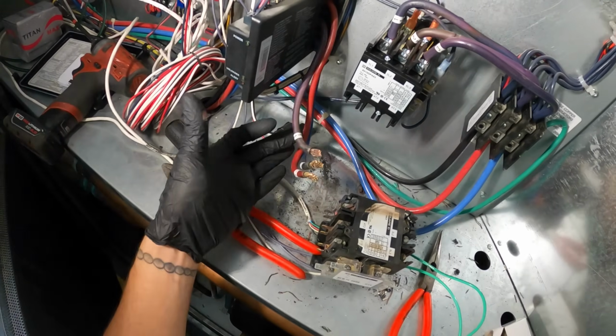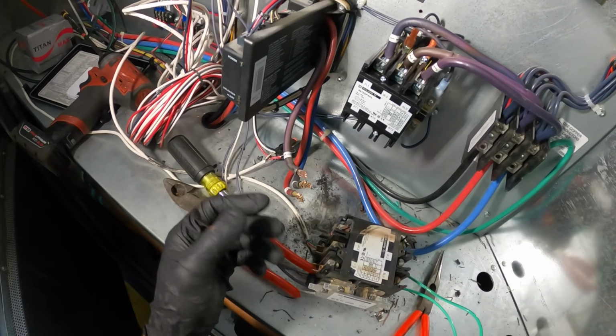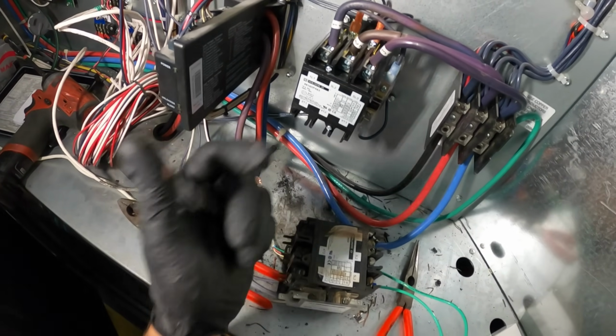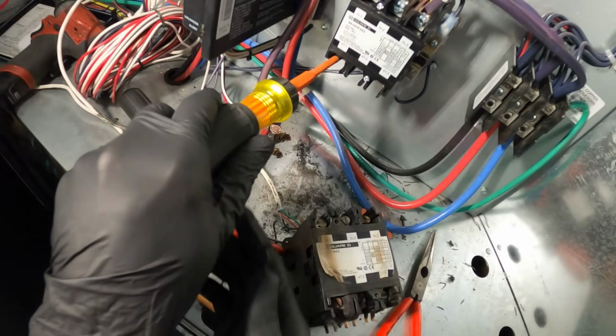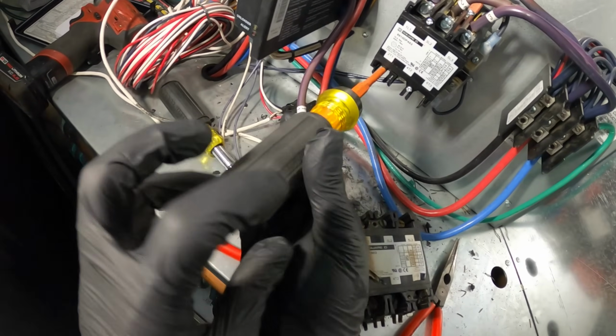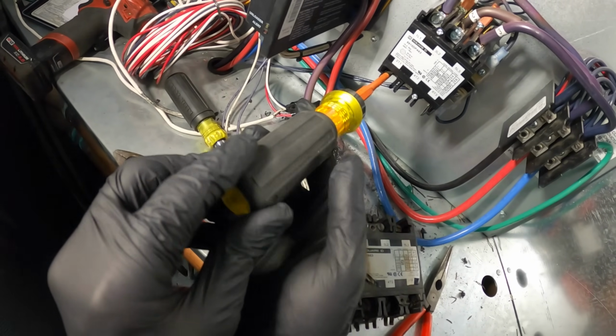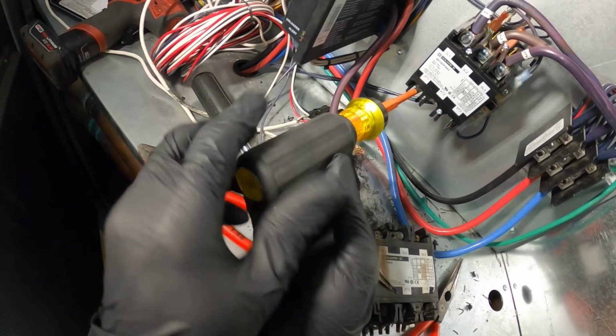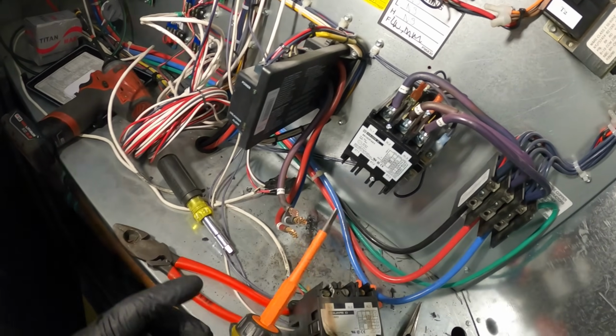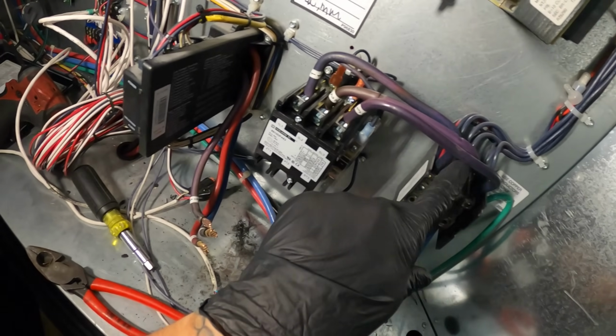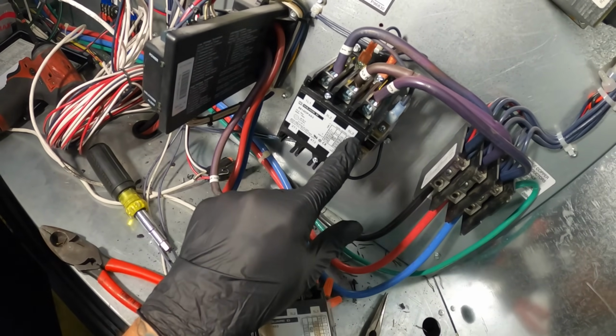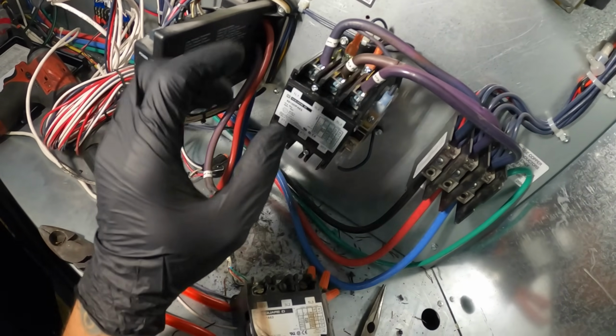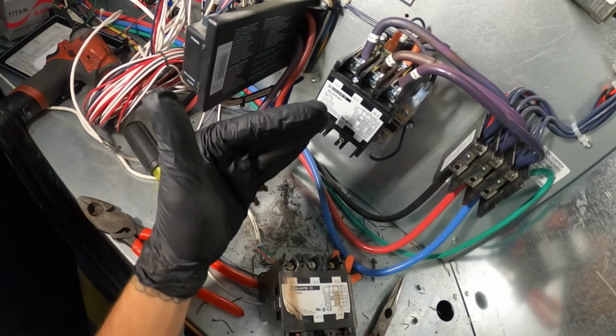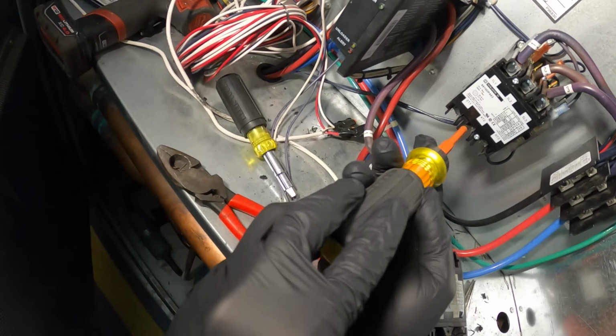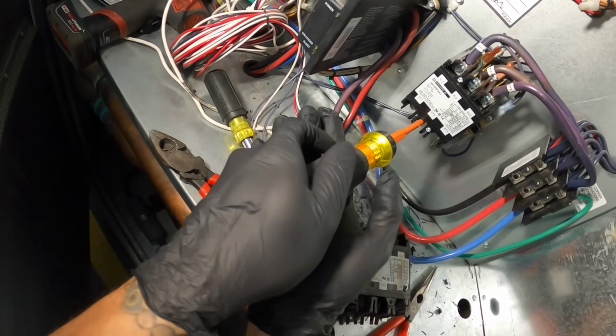And now we just got to put in our 3 load wires, which are labeled 1, 2, and 3. I mean, technically, you can kind of have this contactor upside down, T1 or L1, but that's the way it really should be. On L1, L2, L3 we should have the line voltage, and T1, T2, T3 should be your load. But honestly, either one works.